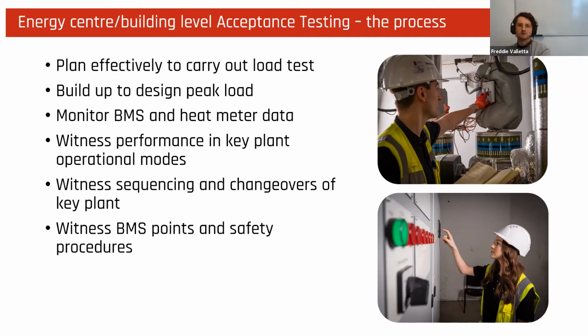Heat meter data becomes incredibly useful at this stage as flow and demand can be monitored at all points in the system alongside your temperature and pressure data obtained from your BMS. Should say that Sula touched on in her presentation the idea of seasonal commissioning. And yes, again, this is when your BMS and heat meter data can be included to fully prove the system performance over a period of time.